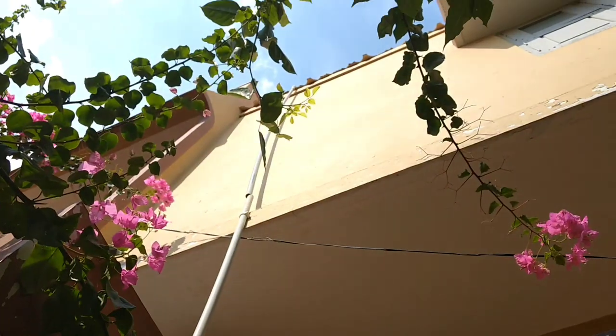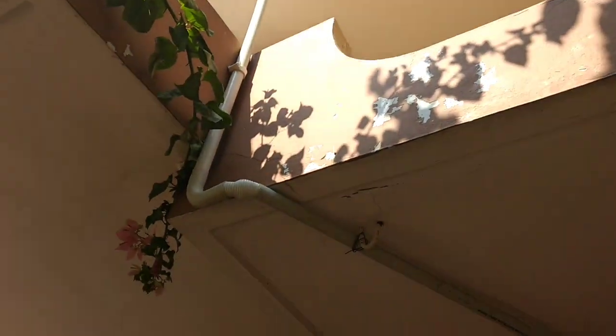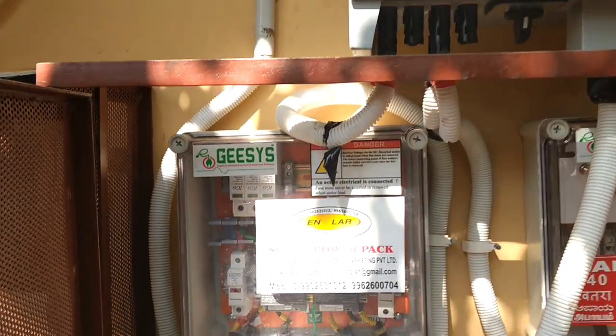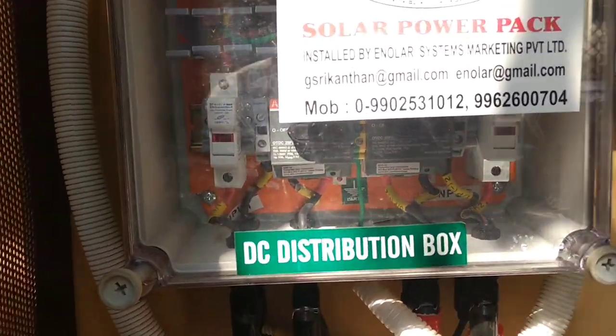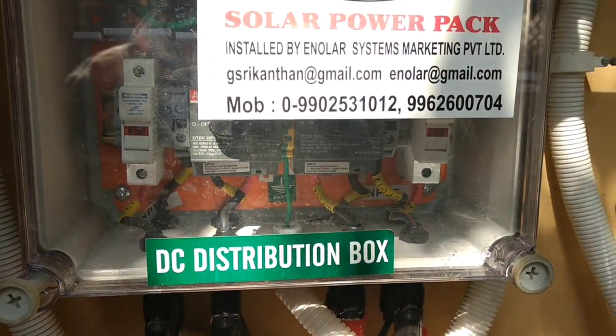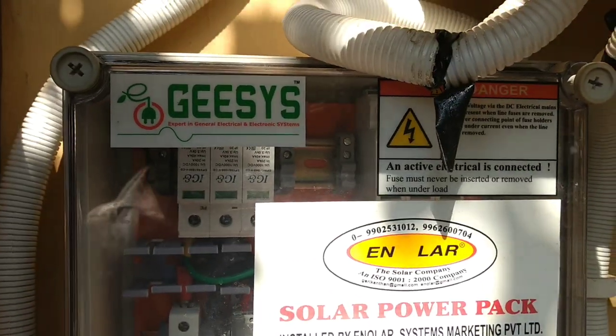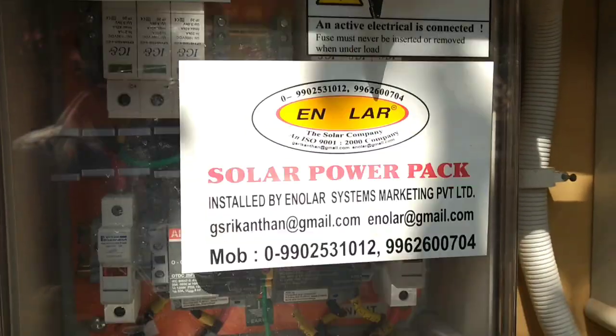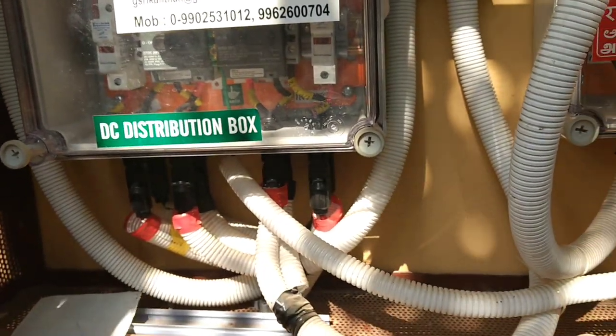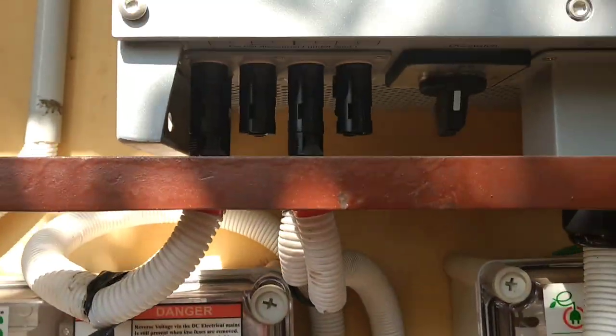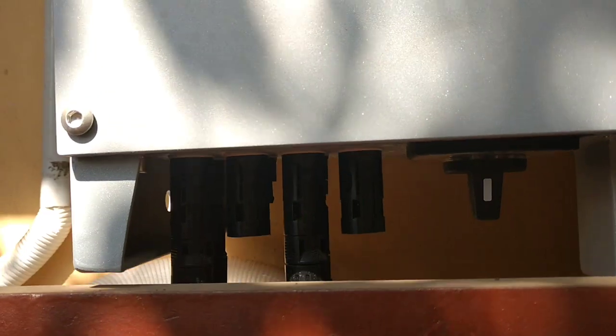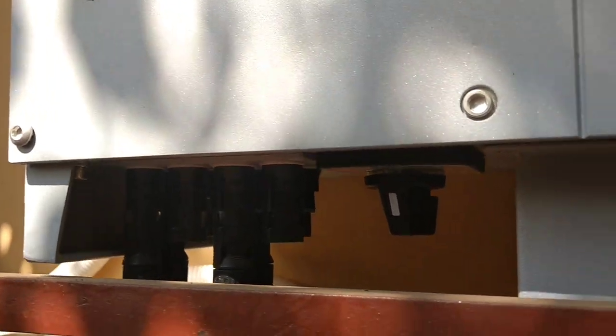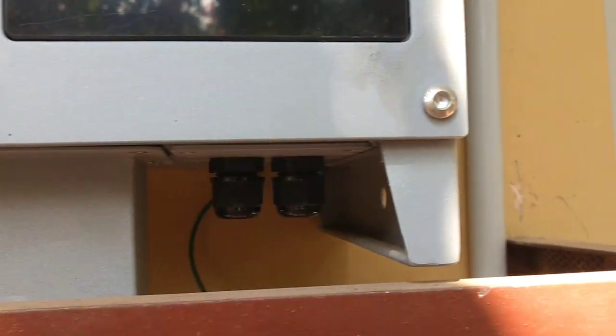Now you can see a plastic pipe which is coming from the rooftop. This is the DC wire from the solar panels which goes inside this DC distribution box. Here we have the DC fuse and the DC surge arrestor. From this isolation, the DC wire goes back into the inverter. Here you can see the MC4 connectors and the strings.